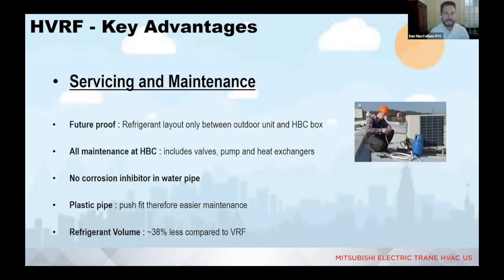On the servicing and maintenance side, it is, in my opinion, a nice benefit that all of the valves, pumps, heat exchangers, all that equipment is located inside the hybrid BC controller. So for those of you who are familiar with a typical heat recovery VRF system, there are piping limitations from the BC controller to each indoor unit that you have to be mindful of. You still do with the HVRF system, but those water pumps that are needed to get the water to the fan coil units are built directly into the hybrid BC box. So you don't have to have an external water valve or water pump to get your water flowing to a unit that's relatively far away from the hybrid BC. The only thing you won't be able to include inside that BC box is the expansion tank that you would need on the water side.